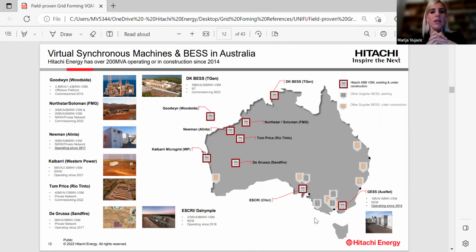The last one I want to mention here is TGen, the project you can see in the north of Australia. It's a 35 MVA, 35 megawatt-hour system, which is under commissioning right now, and will provide all those services such as inertia and system strength, but the customer is also looking into benefiting from 1 hour of energy capacity to provide some additional energy services. What we can also see here is, as I said earlier, the evolution from power applications, so a relatively short duration of the battery energy storage system, towards 1 to 2 hour duration BESS systems.